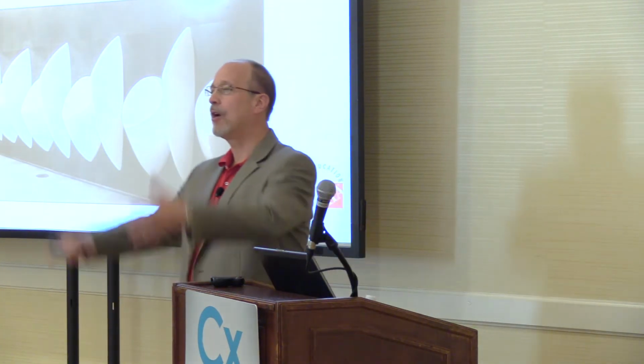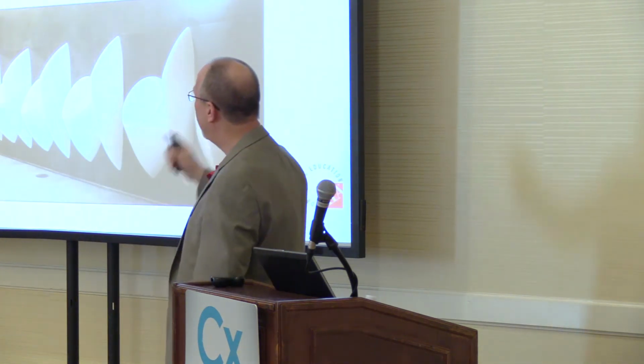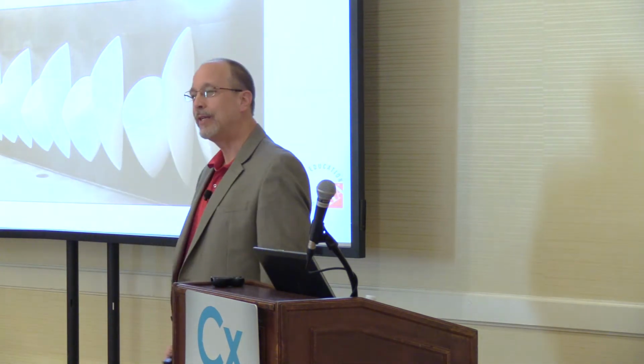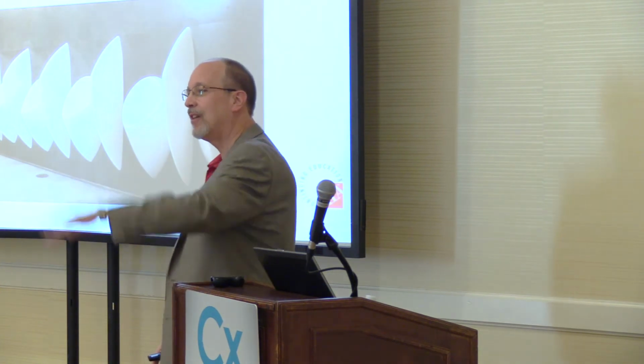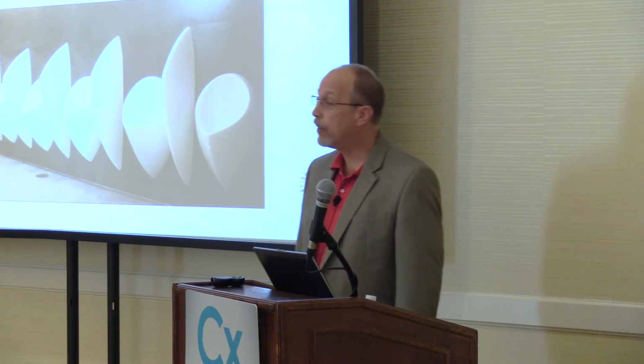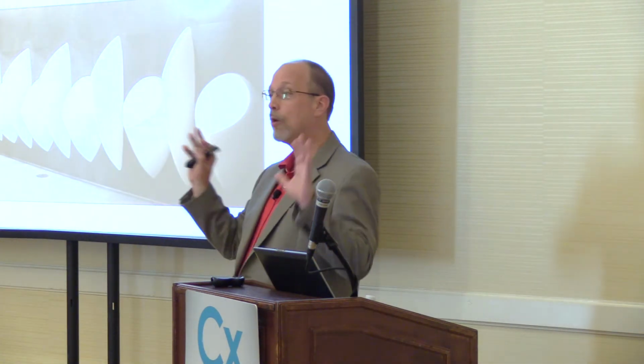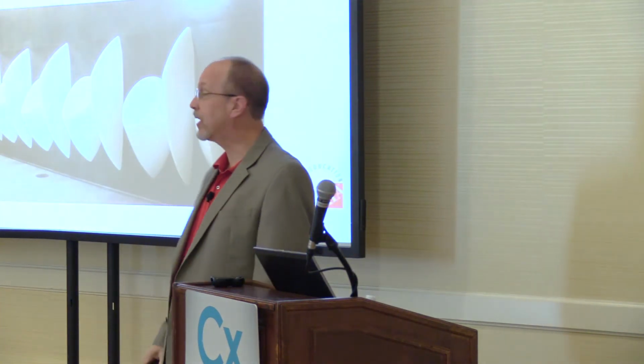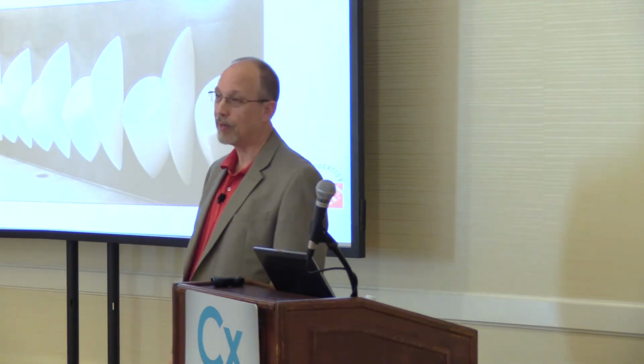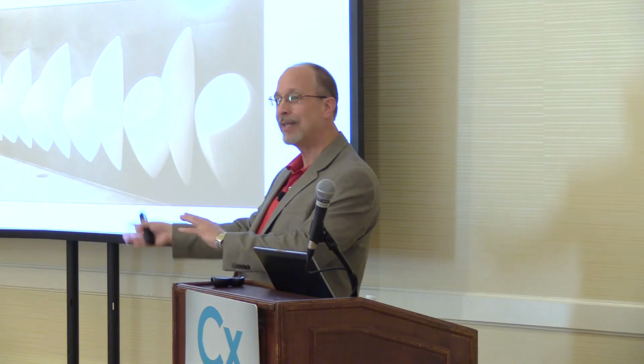Can you imagine a large facility there and every level has a restroom on it? And we just talked about a couple, 3, 4, 5 flushes, maybe 9, 10 gallons every time we flush the toilet throughout the day for hundreds of people there. That's a lot of water. So the rage is, let's see how much water we can save. First thing is justification, because in order to install this, it's a major renovation to the building and the plumbing system there. It is not an easy retrofit. So with that in mind, it also has to be done right. There's nothing worse than a waterless urinal system that does not work.